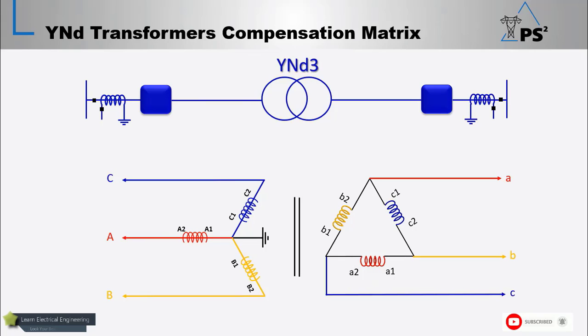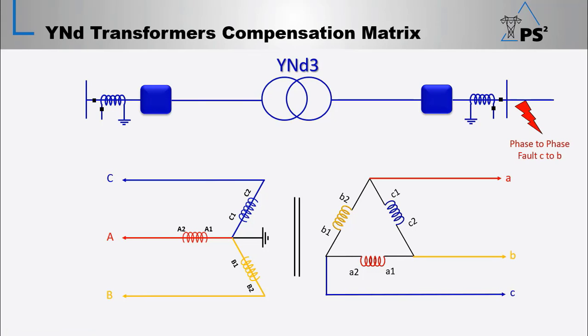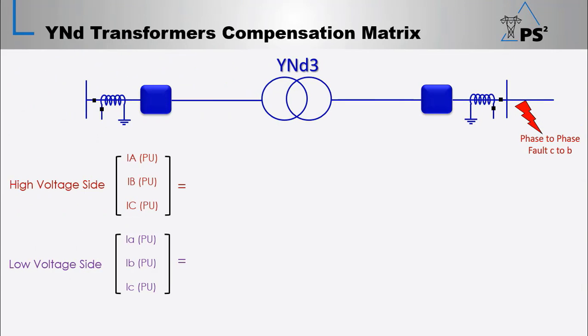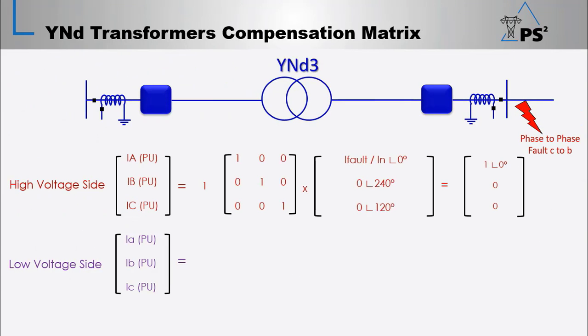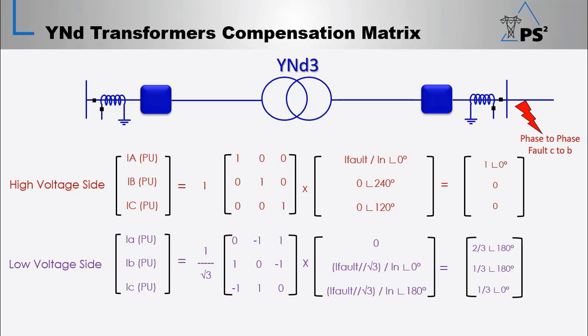If we have a YND3 transformer and a phase-to-phase fault occurred between C and B phases on the delta side, a current will be drawn in the transformer in this direction. Then the per unit currents for the high voltage side would equal 1 angle 0, 0, and 0, assuming that the fault current equals the transformer star rated nominal current. And for the low voltage side, the per unit currents will equal 2 over 3 angle 180 degrees, 1 over 3 angle 180 degrees, 1 over 3 angle 0 degrees. This way, the relay would indicate an instability condition and issue a trip command.